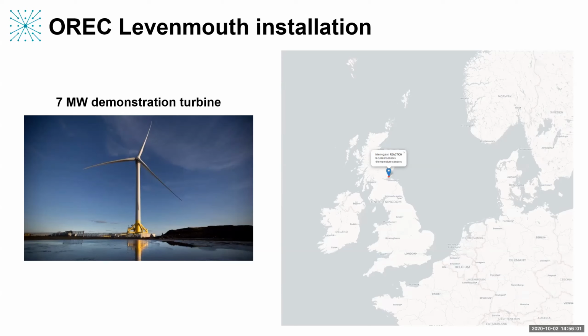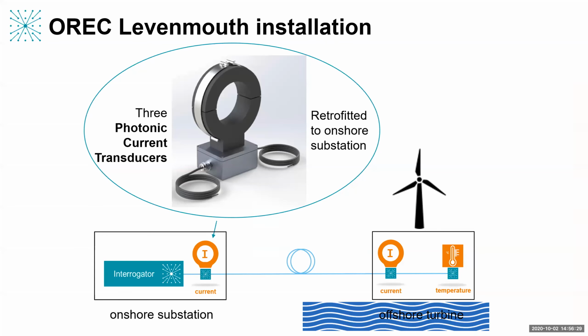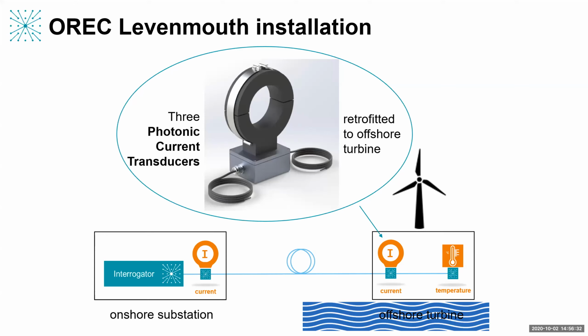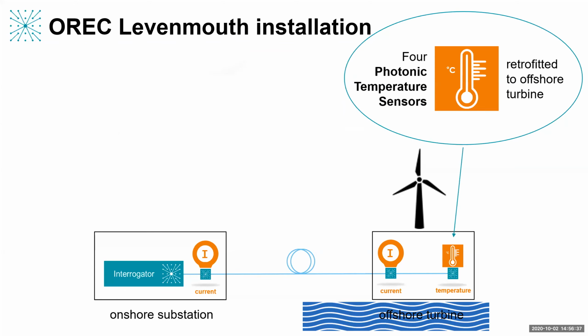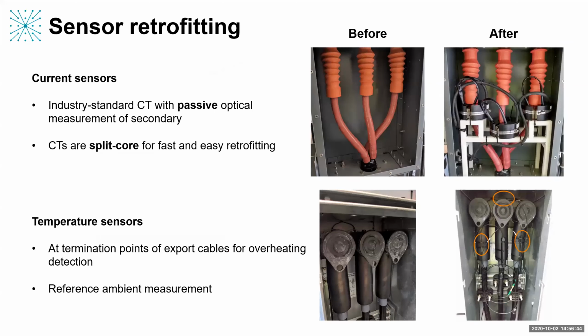What this looks like is we have our interrogator unit, which sits in the substation in the SCADA room onshore, and also onshore we have 3 current sensors bonded to the fiber. Offshore, we have another set of current sensors, and also 4 temperature sensors strategically located inside the turbine. Here you can see the installation - it's a little bit messy, but you can see there's no power supplies, or anything else, or copper connections. There's nothing additional we had to install, just the CTs and the optical fiber.